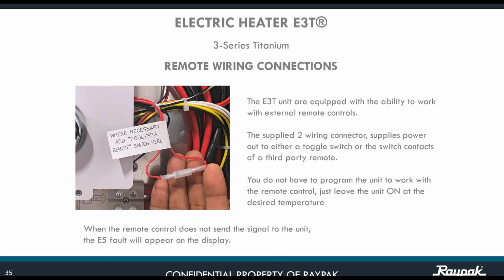Okay, the supply two-wire connector goes right here. What you need to do is disconnect that one and make the connection to the wires that you're going to bring from the automation system. Just make sure that at the automation system, there are two types of connections. One is for a gas heater, and the other one is for an electric heater. So you make the connection where it says electric heater, in order to follow the proper flow of voltage inside of the automation system.